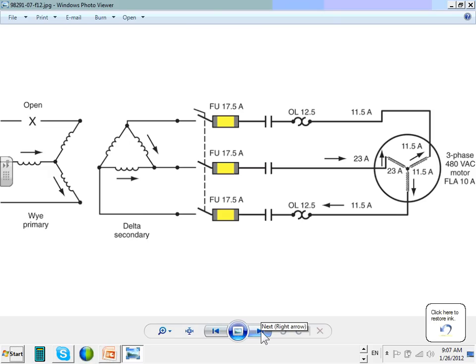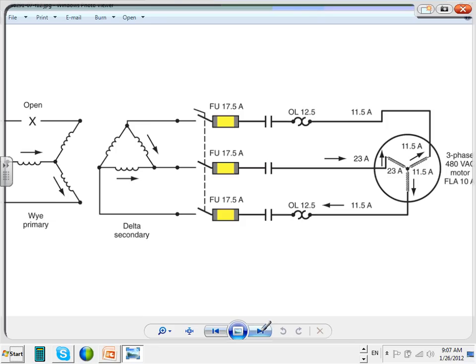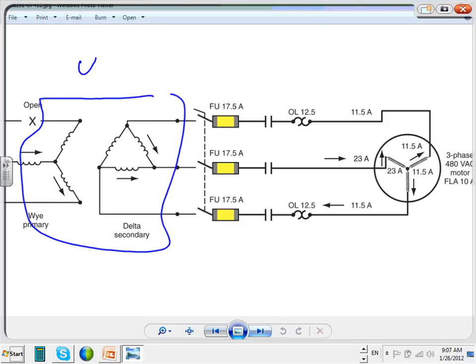Now look what happened. Now if you have a single phase, guys, on the primary, this is your utility transformer. This is utility, and on the transmission line 13.8, this is a 13.8 system. Okay, I lost one line, right? A fuse on the transmission from the utility. Now your building has a delta-Y feed coming in. Then look, the same thing is going to happen, guys. The currents are going to be different, but because you lost one phase, the delta compensates for the third phase. If you have a delta, the delta coils will compensate for the last phase on the primary of the transformer, and it will give you some current. In this case, the phase that you lost on the primary continues on the secondary to pull 11.5, but to compensate for the loss, one phase will be pulling 23 extra.